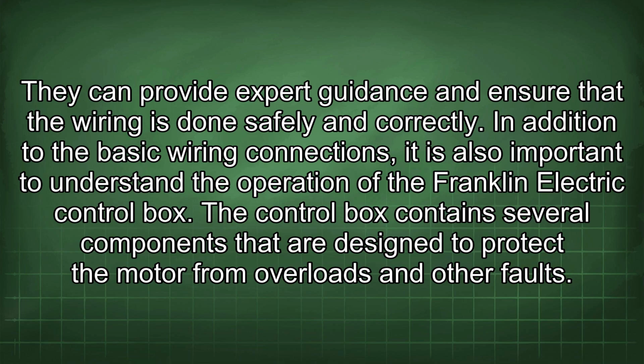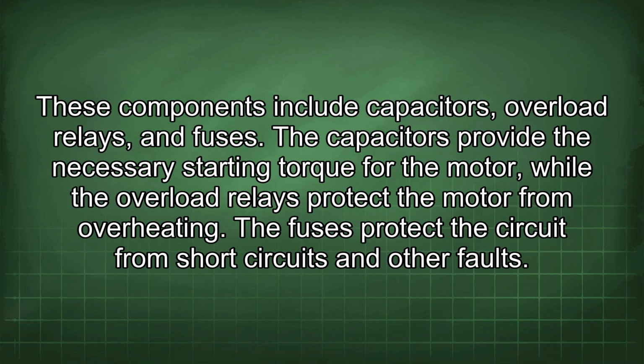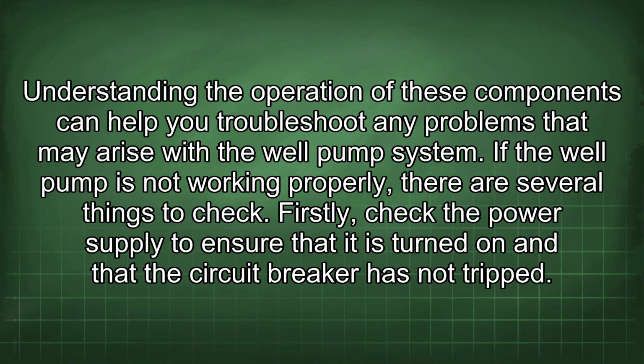In addition to the basic wiring connections, it is also important to understand the operation of the Franklin Electric control box. The control box contains several components that are designed to protect the motor from overloads and other faults. These components include capacitors, overload relays, and fuses. The capacitors provide the necessary starting torque for the motor, while the overload relays protect the motor from overheating. The fuses protect the circuit from short circuits and other faults. Understanding the operation of these components can help you troubleshoot any problems that may arise with the well pump system.